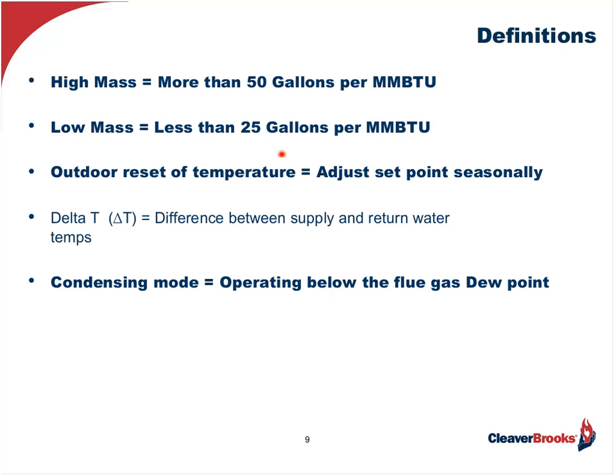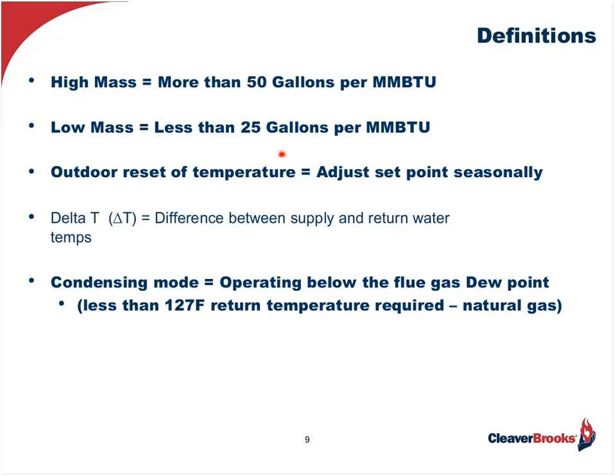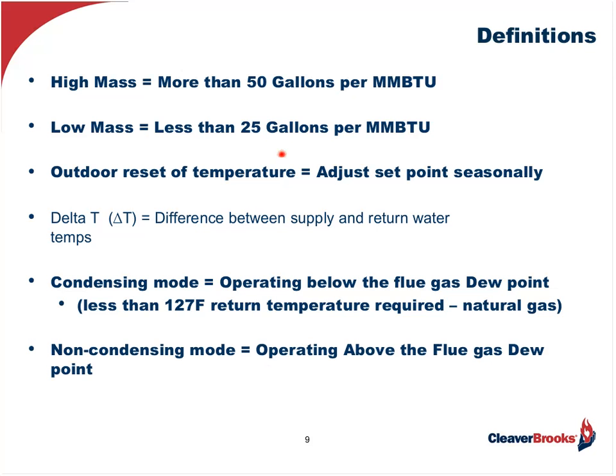And then condensing mode, which is any time we have a return water temperature less than 127 degrees. That's a nominal temperature. It's going to depend on the makeup of the natural gas. Non-condensing mode is any time you have a return temperature greater than 127. The important point to remember here is that any boiler will condense if that water is cold enough. It's just that some boilers, that's an undesirable condition.